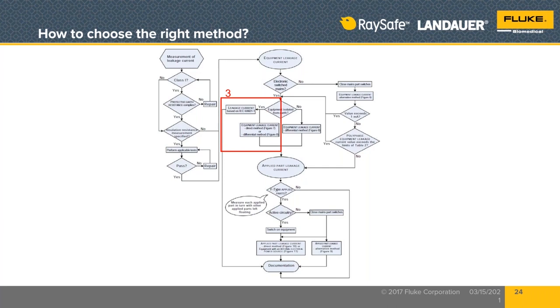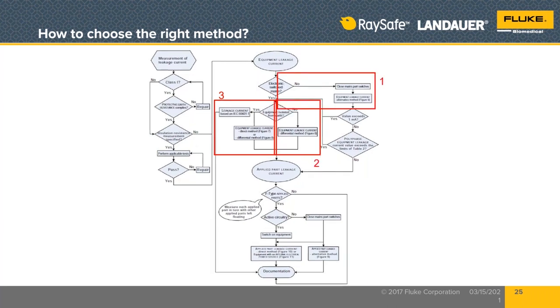Okay. And the reason we would pick direct method is because the test results will be the most like the results that were gotten using IEC 60601-1 in the factory and final assembly testing, or in the design validation testing before, as the medical device was proven to be safe and effective for clinical use. All right, so those are our big decision points about which method.